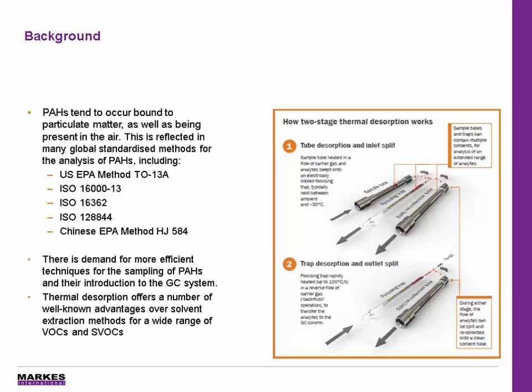The focusing trap is then heated up in the second stage of thermal desorption, and a reverse flow of gas through the focusing trap transfers the compounds of interest to the GC column and to the detector. At this point we can also split for a second time — termed the outlet split — where the vapours of interest can be taken onto a clean sorbent tube and recollected. These tubes can then be re-analysed at a later date.